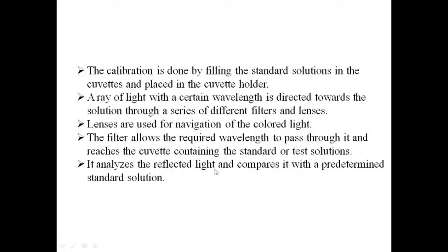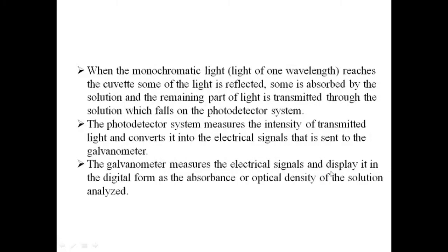It analyzes the reflected light and compares it with the predetermined standard solution. When the monochromatic light, that is, light of only one wavelength, not a range of wavelengths, a specific wavelength is decided, this reaches the cuvette.